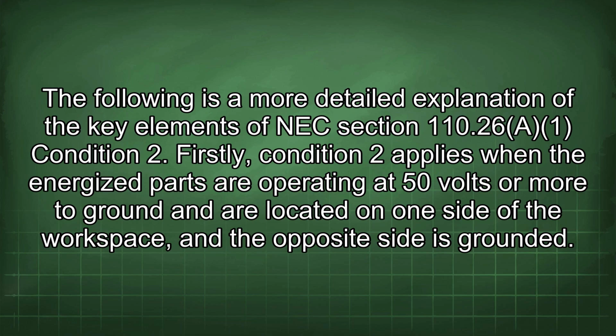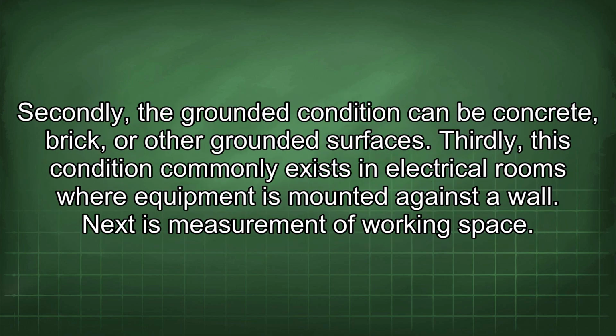Following is a more detailed explanation of the key elements of NEC Section 110.26 Condition 2. Firstly, Condition 2 applies when the energized parts are operating at 50 volts or more to ground and are located on one side of the workspace, and the opposite side is grounded. Secondly, the grounded condition can be concrete, brick, or other grounded surfaces. Thirdly, this condition commonly exists in electrical rooms where equipment is mounted against a wall.